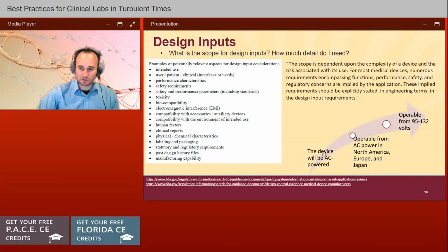I'll go over one example of how to go from vague and broad into narrow on a design input. So if you look at the figure in the bottom right, we start with the device will be AC powered. Okay, that's helpful, but not specific, quantifiable, objective. And so I'm going to X that out, and I'm going to go to the next stage. Well, I want my device to be operable from AC power in North America, Europe, and Japan. Once again, helpful, but not quite specific enough. Typically, systems run at 120 volts, but many systems are designed to operate over a range. And if it's a critical device, then you probably want around 95 to 132 volts to account for brownouts or other potential problems that happen.